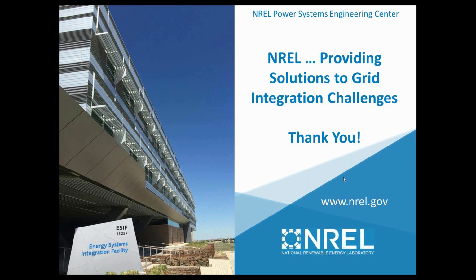So I think you'd have to look at additional factors that may help you determine whether or not you need to require some form of embedded communications. Again, as we discussed on those slides, some of those things look like the number of inverters that you have, whether you have a mix of different inverter technologies, and getting a better understanding of what kind of unintentional islanding or active anti-islanding techniques those systems may be using. I'd say, based on the experience we have to date, that inverters that use active anti-islanding do a very good job of detecting island conditions and disconnecting from the grid quickly. I hope that answers that question.